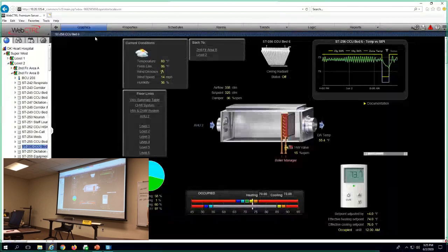Is that across the board in every space? It should be in every space. When we're communicating with end users, it's good for us to know this. So when we go to the nurse's station and they say it's 73, and you look at it and it's on +1, we're educating the end users that your base set point is 70. If you want to go 4 degrees above that, you punch it up to +4. You want to go 4 below it, you punch it down. Is that appropriate to communicate?